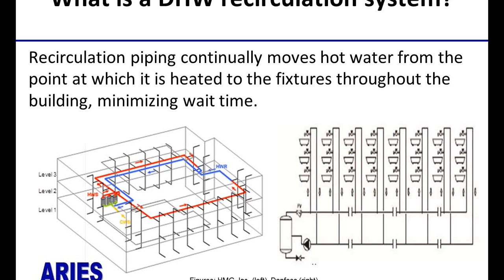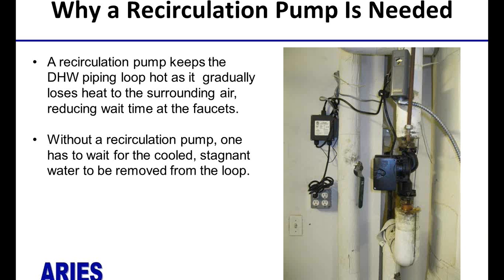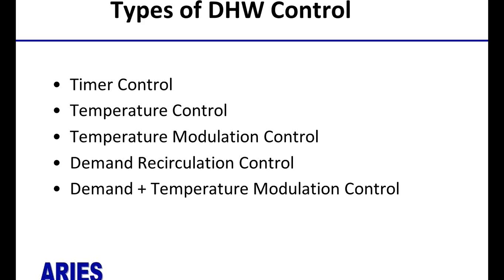So why do we have these systems? Primarily to reduce wait time at the tap for users. You can see this diagram. The two diagrams here show typical systems. With a water heater, there is a supply line and then a return line that brings it back to the water heater. And that pump keeps the lines hot so that wait time at the tap is minimized.